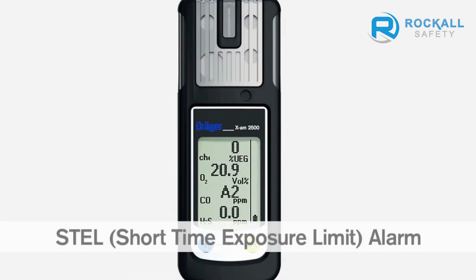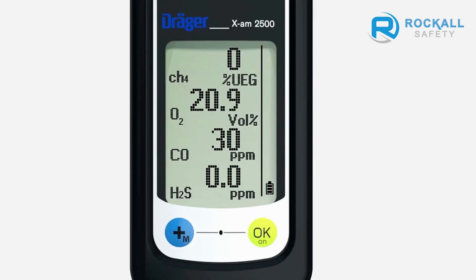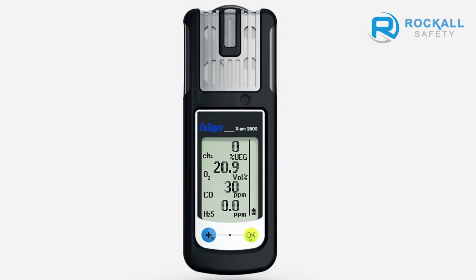This is how to recognize an STEL alarm. The audible, visual, and vibration alarms are repeated periodically. The STEL symbol flashes in the display on the right. The gas concentration alternates with A2 on the left. You must leave the danger zone immediately. The alarm cannot be acknowledged.